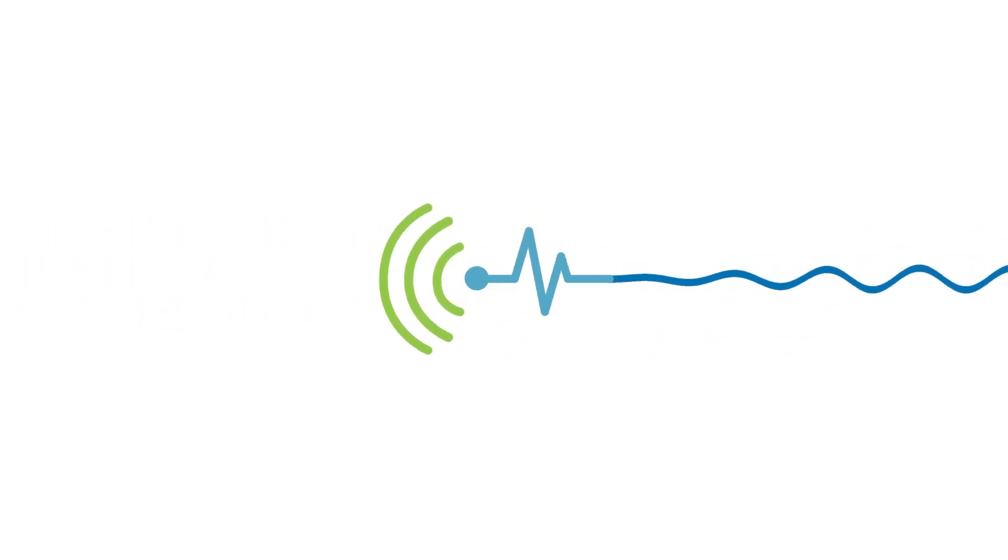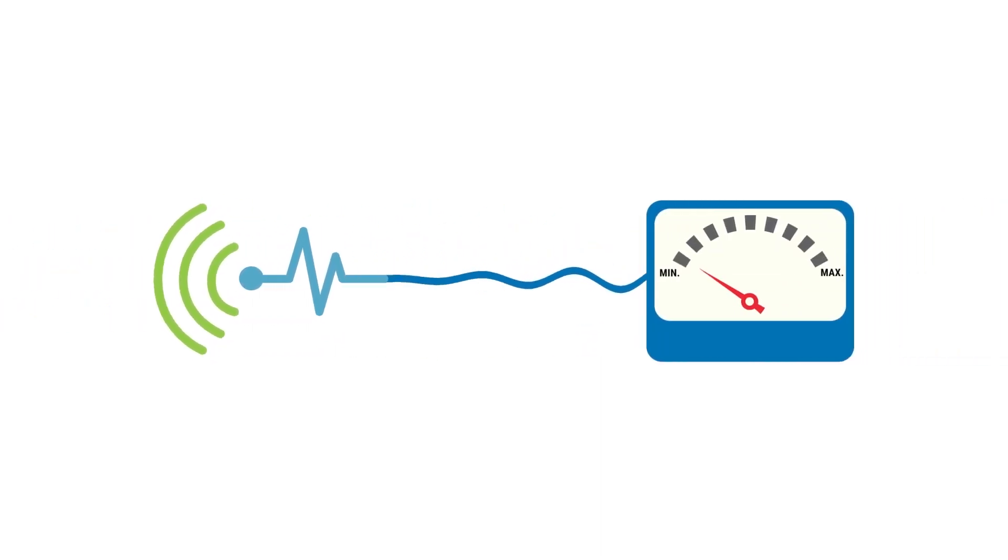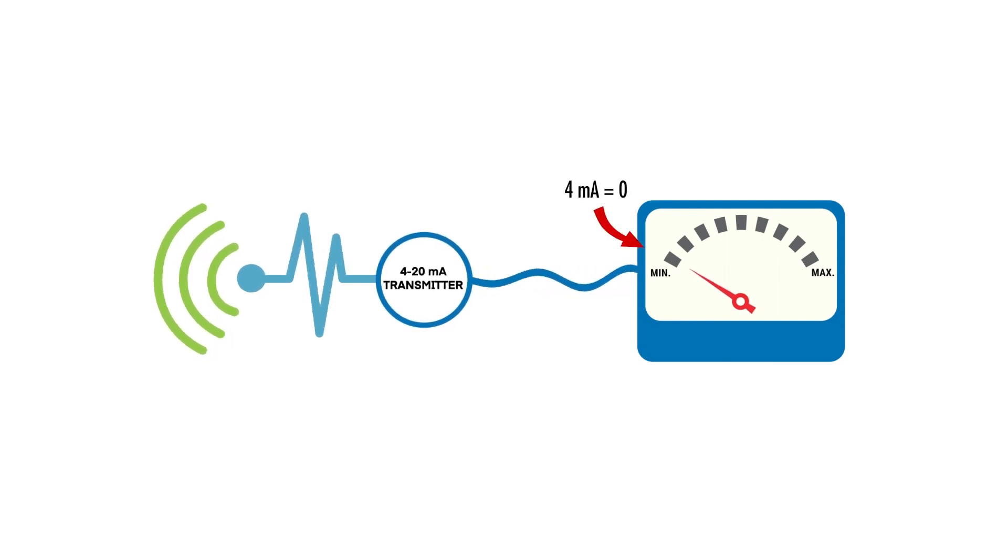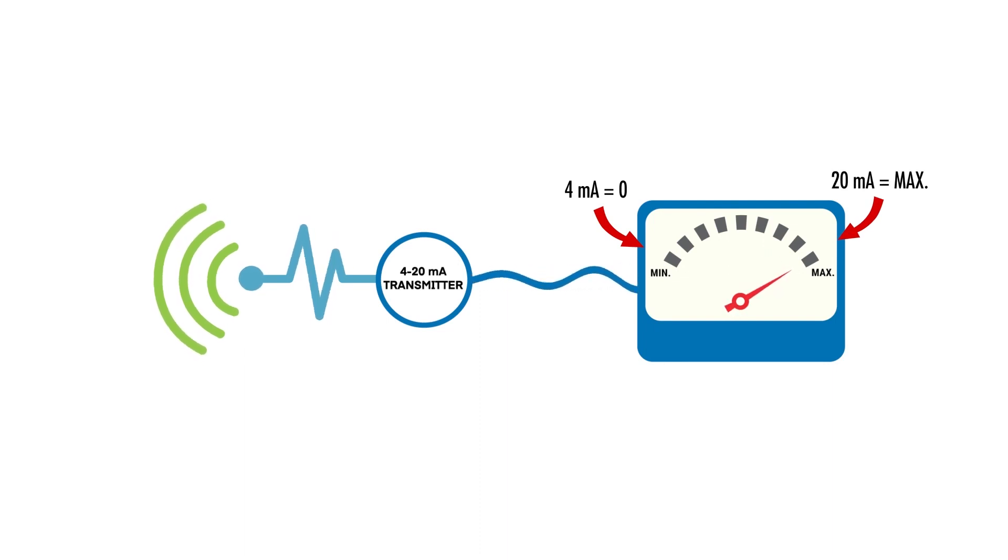Next, let's look at the 4 to 20 milliamp current loop. This very simple yet robust sensor signal standard converts the sensor's output so that the zero point or low threshold reads 4 milliamps in the system, and the highest threshold appears as 20 milliamps.